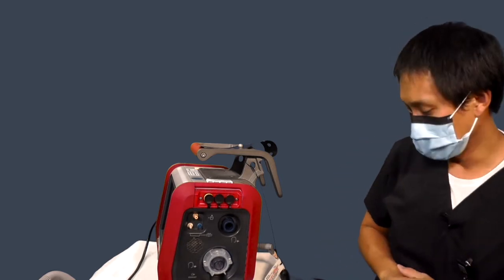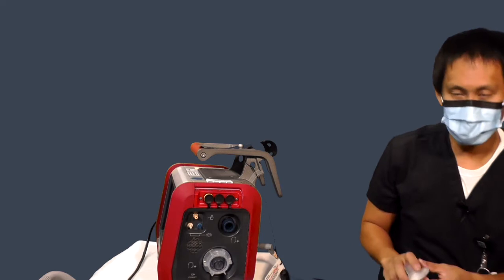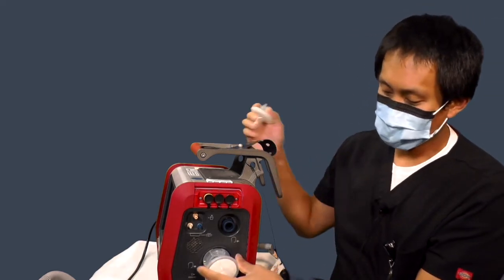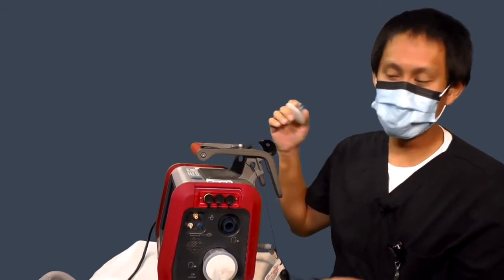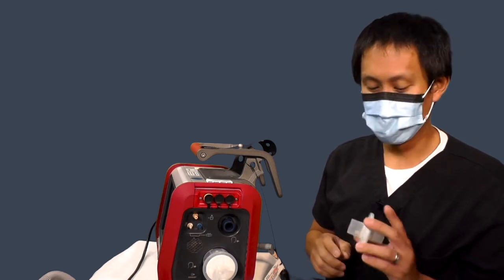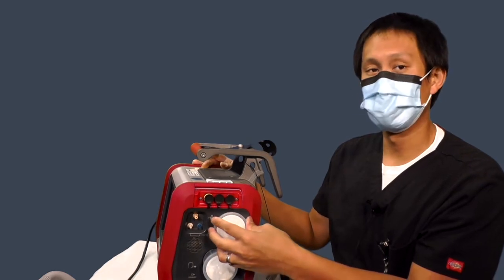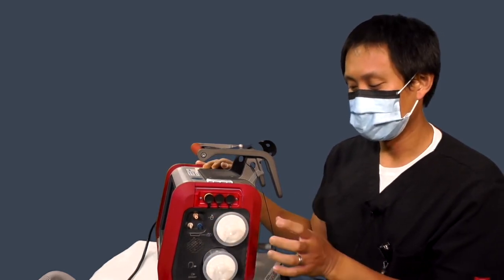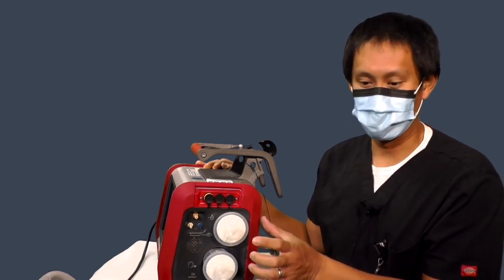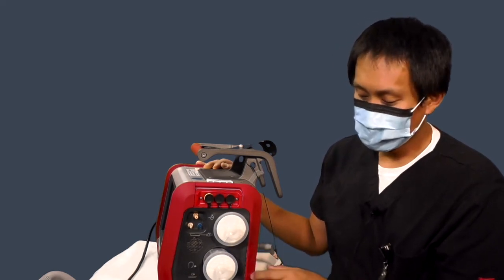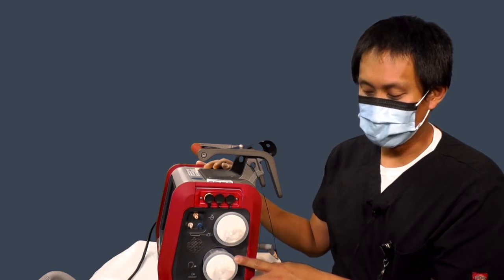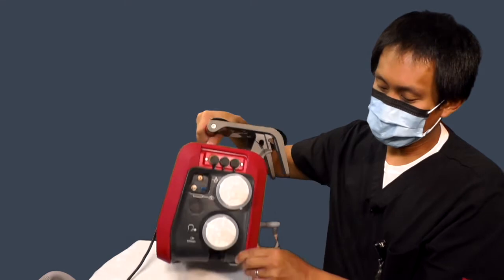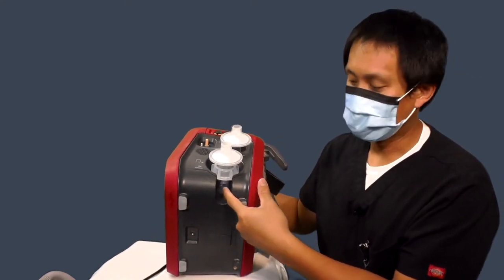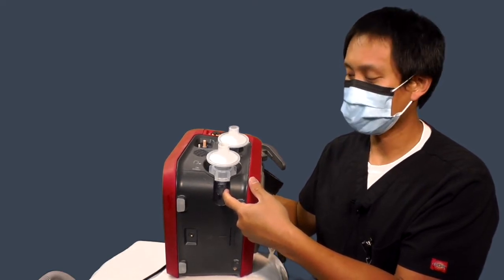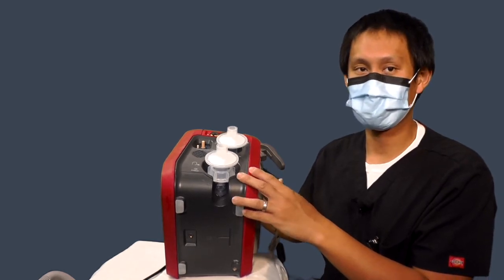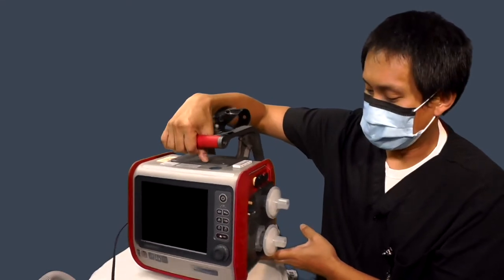The next thing we'll need to do is add our viral bacterial filters. You can use any viral bacterial filters. You'll need one on the expiratory side, and if you're using the Hamilton circuit, you'll also need one for the inhalation side as well, unless you want to cut a piece of tubing to fit the length of the elbow on the Hamilton circuit. And you'll see in a second what I mean. You'll definitely need a filter on the expiratory side, and the reason for that is the exhalation from the patient comes out from the bottom of your exhalation valve. So this is not only to protect the ventilator, but it is to protect yourself as well from anything that the patient has.